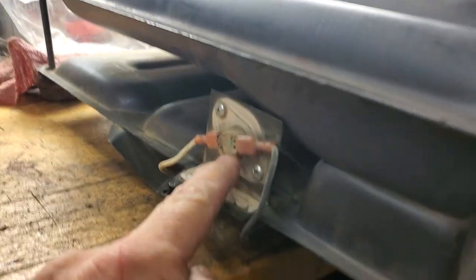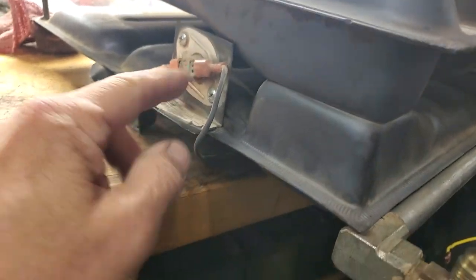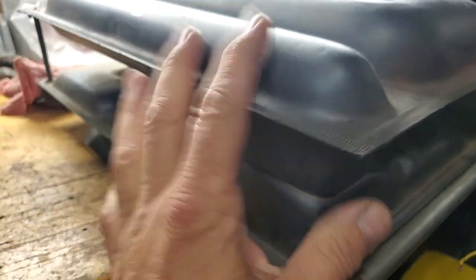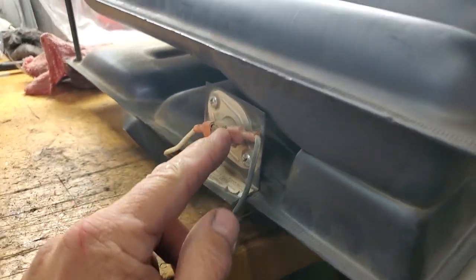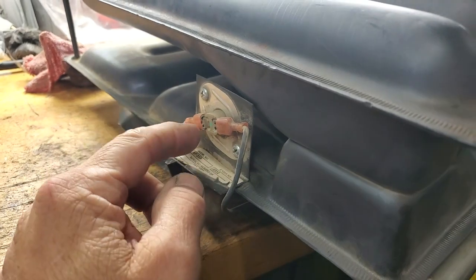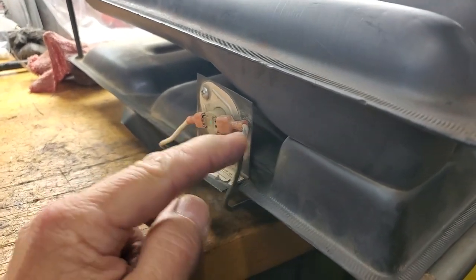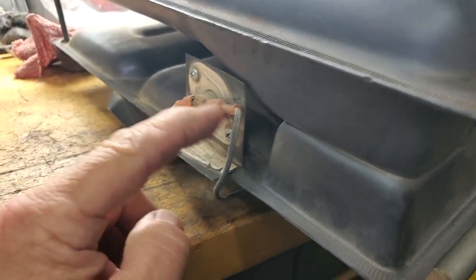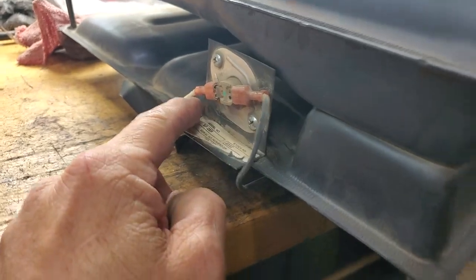There's two things that have to happen. One, you're going to command the blower motor on, say hey turn on the heater, no, the blower motor comes on. This is the over temp switch. That means that this heat exchanger got too hot and it opened. Right now it's closed, that means voltage flows through here, like a draw bridge that's closed.